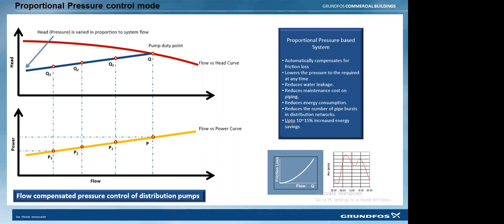So then automatically, instead of maintaining a constant pressure, your curve itself will get shifted to a lesser operating pressure based on your flow rate. Instead of maintaining a higher pressure, whenever there is a lower flow, your pressure also will come down. So this will help us avoid continuous stress on your pipeline. Otherwise, your system will be stressed.